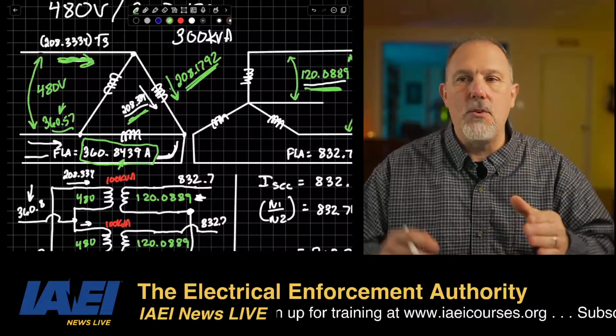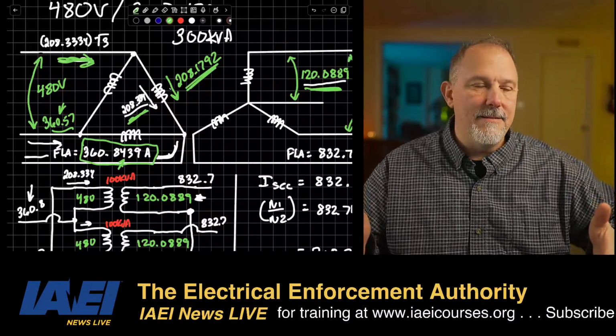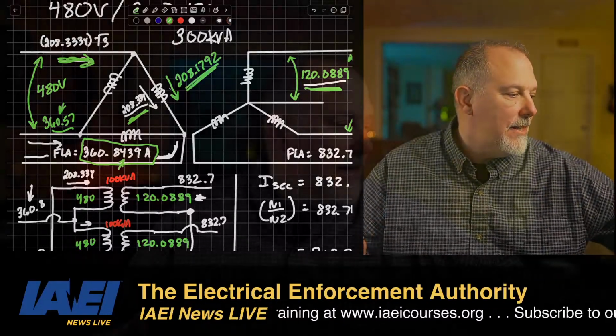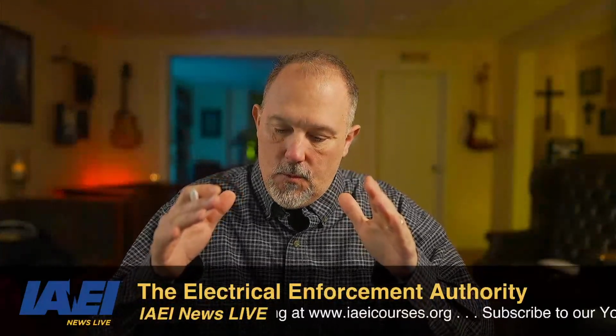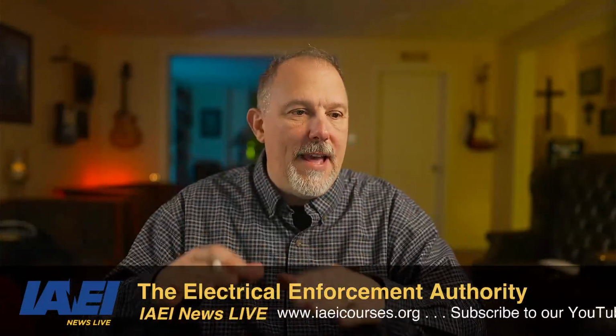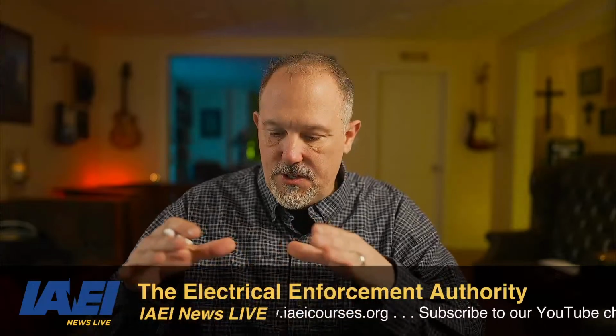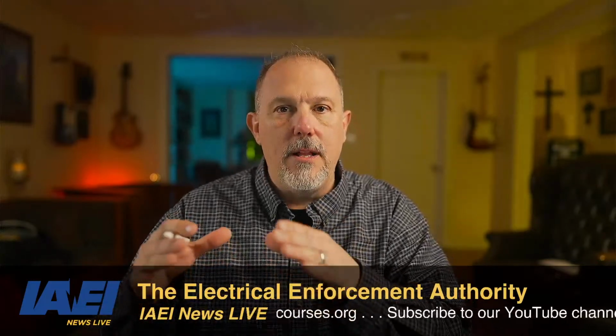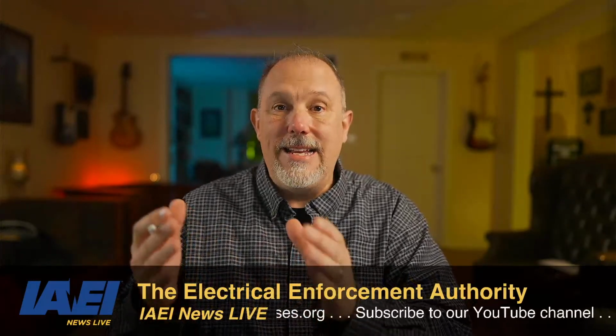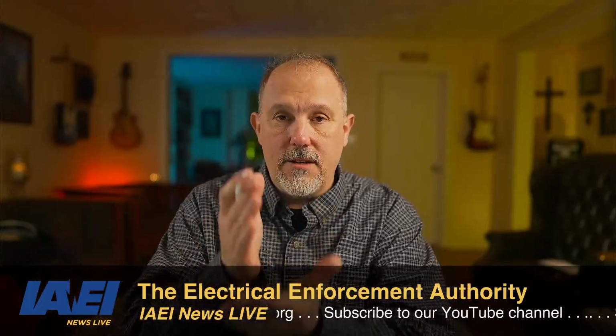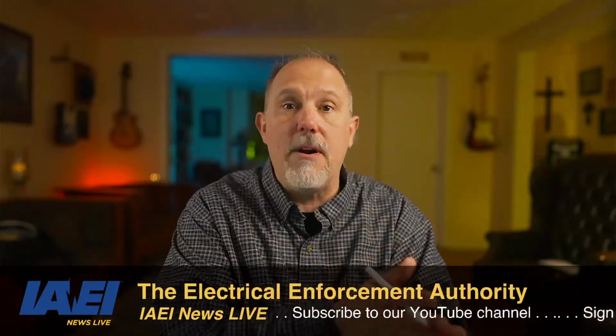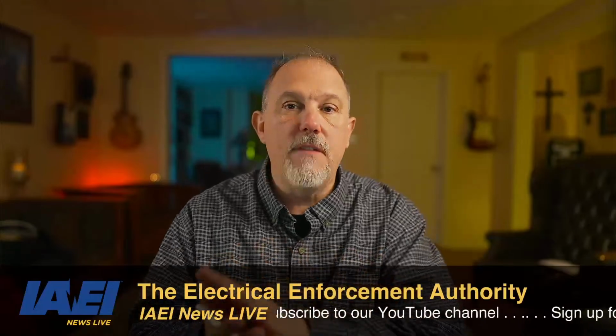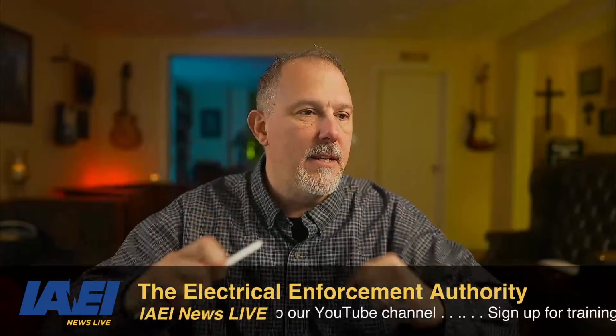That's why you can't do line to line to line to line, which would be wrong, right? So what I've tried to do in that example is give you a little flavor for an easy way to do it. You calculate the full load amps on the secondary or the primary, whichever, and just reflect the current to the primary.